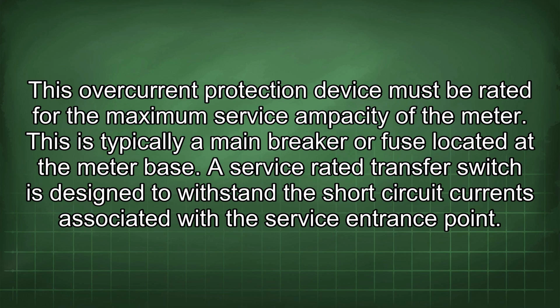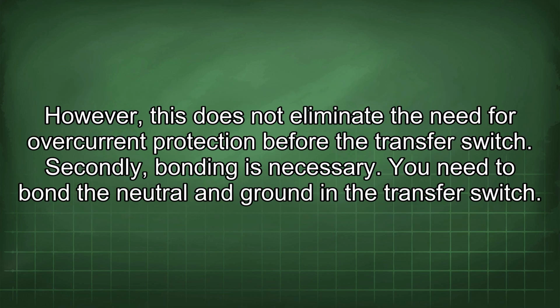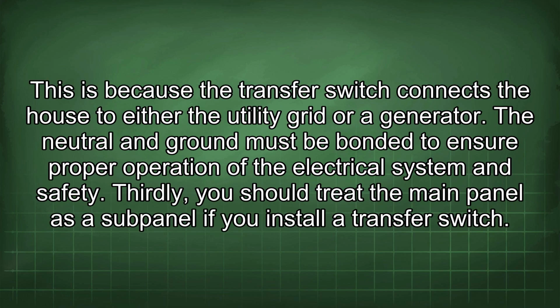A service-rated transfer switch is designed to withstand the short-circuit currents associated with the service entrance point. However, this does not eliminate the need for overcurrent protection before the transfer switch. Secondly, bonding is necessary. You need to bond the neutral and ground in the transfer switch. This is because the transfer switch connects the house to either the utility grid or a generator. The neutral and ground must be bonded to ensure proper operation of the electrical system and safety.